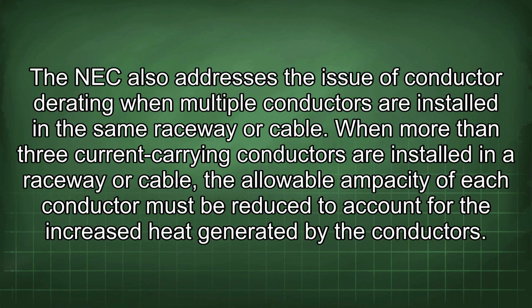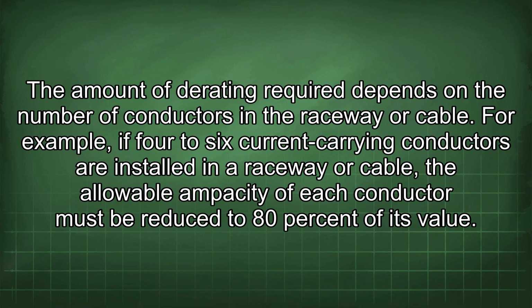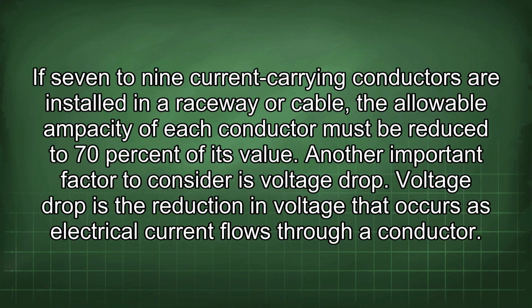The NEC also addresses the issue of conductor derating when multiple conductors are installed in the same raceway or cable. When more than 3 current-carrying conductors are installed in a raceway or cable, the allowable ampacity of each conductor must be reduced to account for the increased heat generated by the conductors. The amount of derating required depends on the number of conductors in the raceway or cable. For example, if 4 to 6 current-carrying conductors are installed in a raceway or cable, the allowable ampacity of each conductor must be reduced to 80% of its value. If 7 to 9 current-carrying conductors are installed in a raceway or cable, the allowable ampacity of each conductor must be reduced to 70% of its value.